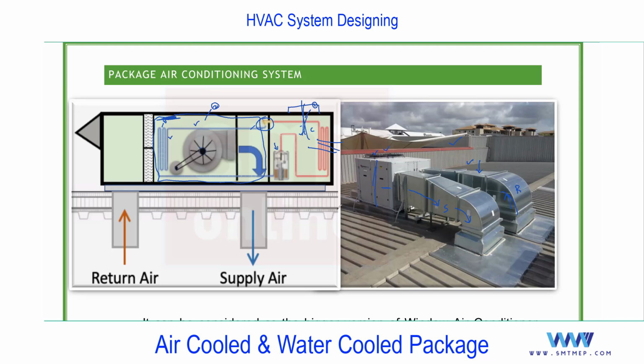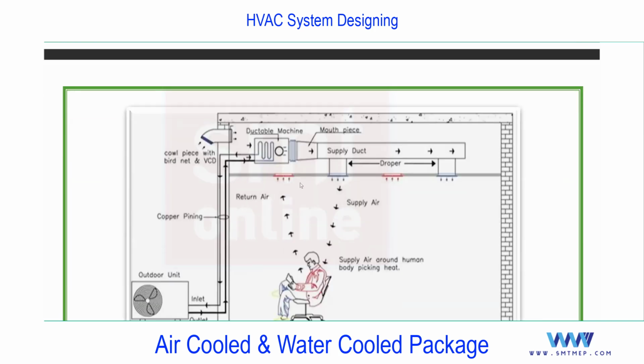Second point, we can attach the duct. I'm talking about the air-cooled system. Water-cooled we'll discuss next. Let me complete the air-cooled. You see, second point, we can attach the duct. In that, we require a supply duct as well as a return duct. In the previous case, the return duct was optional. Let me show you. You see, in this case, there is no return duct. This is called free return, because in all the cases, we don't require the return duct.